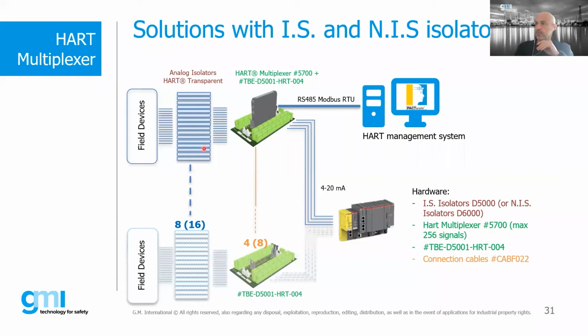This one. Okay, so the loops are here connected to these modules, and the loops go for 4-20mA directly to your PLC. Just an example of PLC. And here the number of isolators can in this case be a group of probably 16 modules, and each group, going to say 2 groups of these, can go to 1 board. That's why in this case, if you have 8 groups of isolators, you can use 4 boards. If you have 16 groups of 16 isolators, you can have 8 boards. So that is a multiple of that.